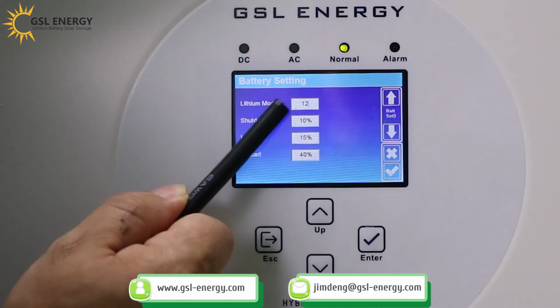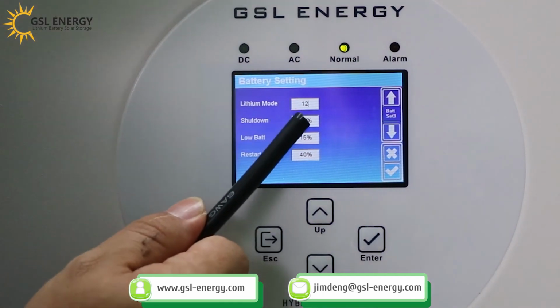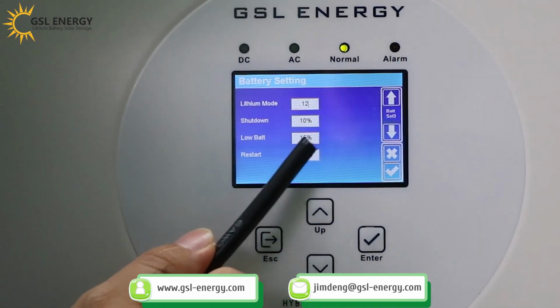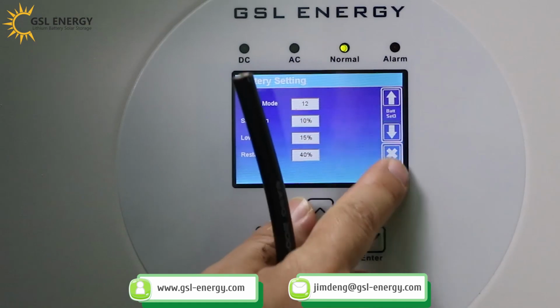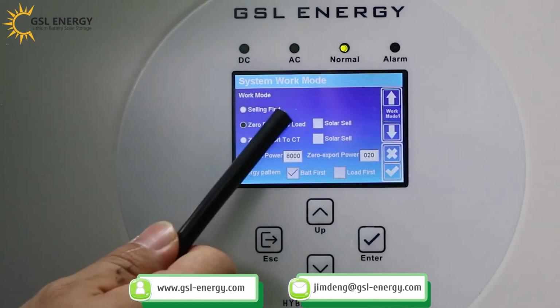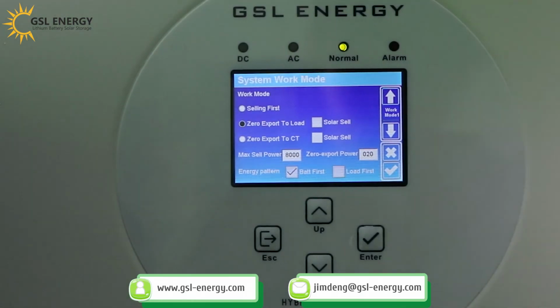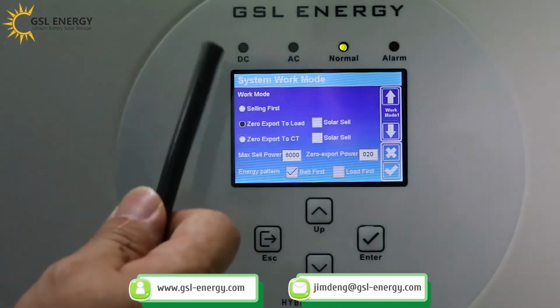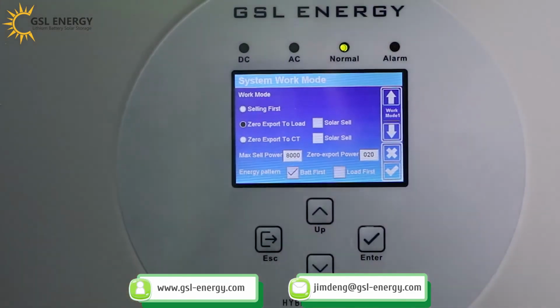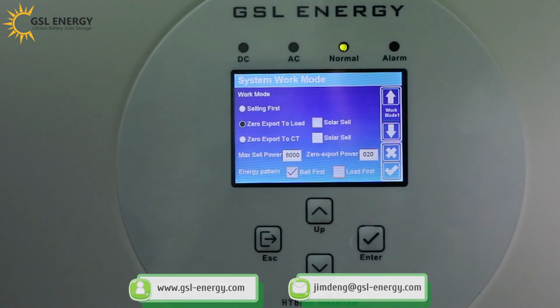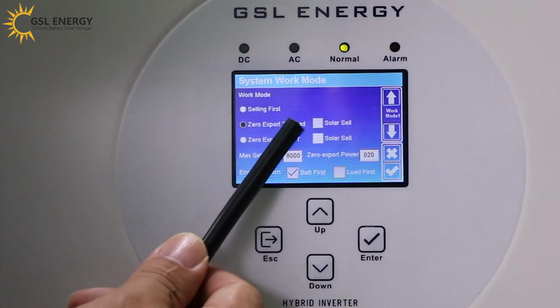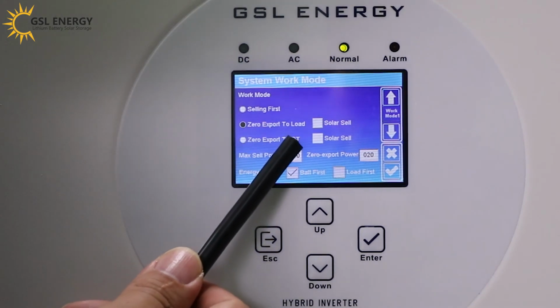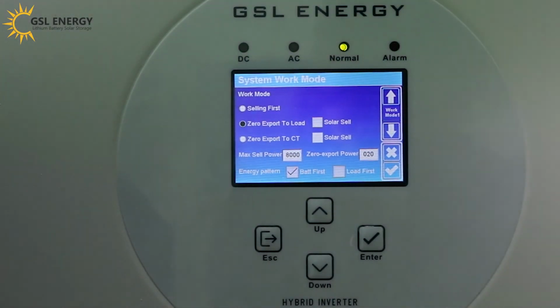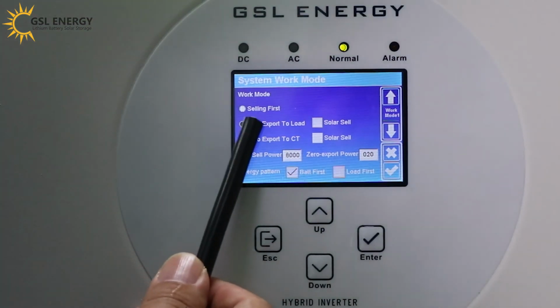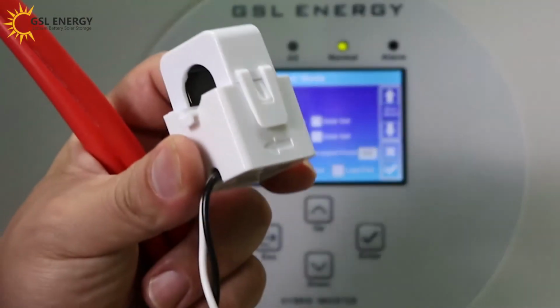Here is very important. Lithium Mode setting 12. Shutdown 10%, low battery 15%, restart 40%. It's right. For the next work mode, selling first. If you want to sell solar panel electric power to the grid, you can choose selling first. If you don't want to sell the power to the grid, you need to choose zero export to load or zero export to CT. If you don't install the CT in the system, you can choose zero export to load. This is the CT, right?